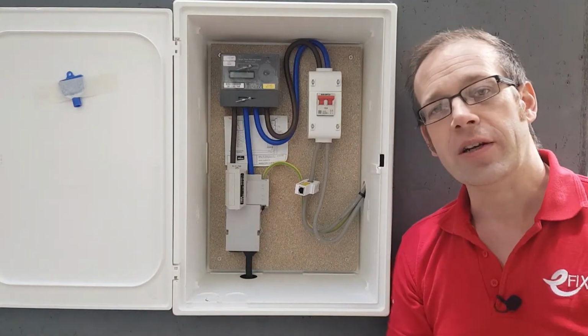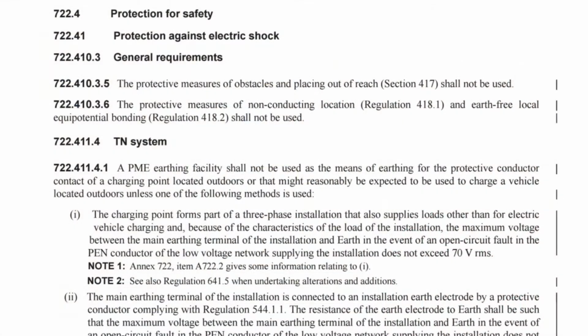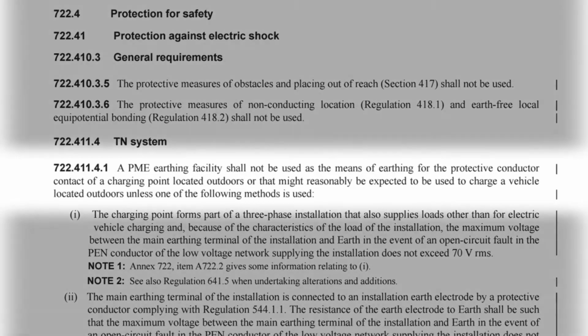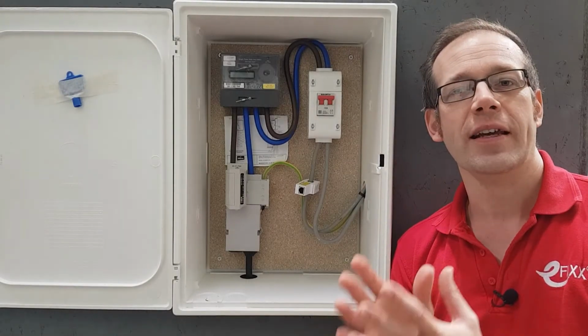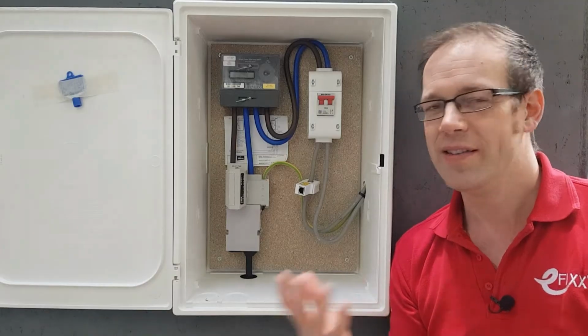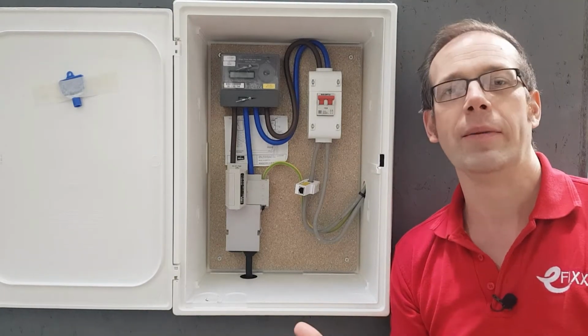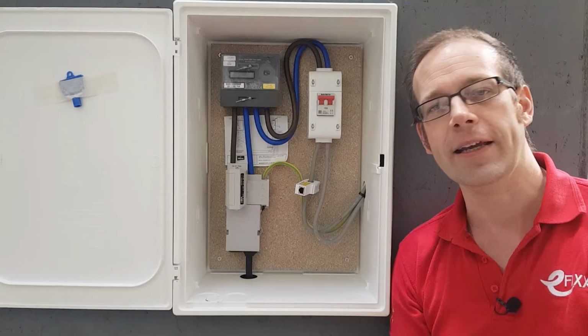We find some information about this in Regulation 722.411.4.1 under the heading TN Systems, where we read, "A PME earthing facility shall not be used as the means of earthing for the protective conductor contact of a charging point located outdoors or that might reasonably be expected to be used to charge a vehicle located outdoors unless one of the following methods is used." Now we'll get to those methods in just a moment. But first of all, why is this regulation in here? Why are we worried about PME earthing for charging EVs?